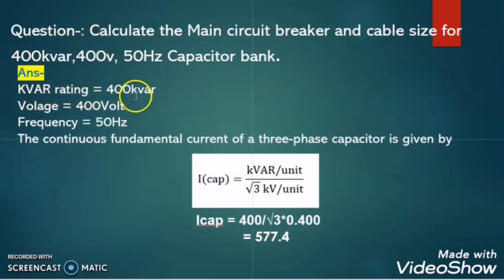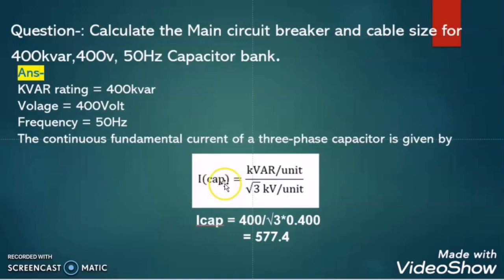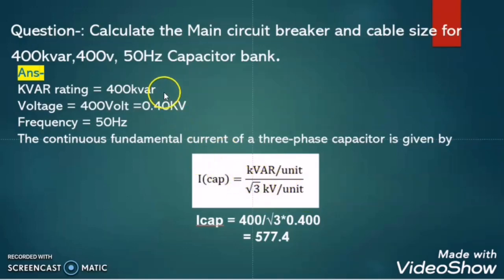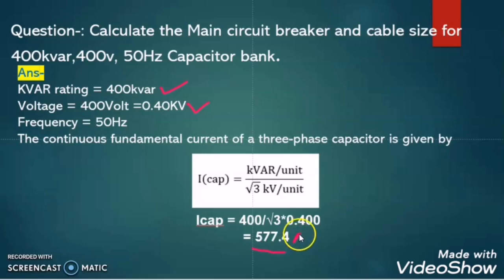I tabulated this information here: the kVAR rating is 400, voltage is 400V and the frequency is 50 Hz. The formula to calculate the current in a capacitor bank is: I = kVAR / (√3 × kV). Here the kVAR value is 400 and the voltage in kV is 0.40 kV. So substituting: 400 divided by (√3 × 0.400 kV), the result comes as 577.4 A.